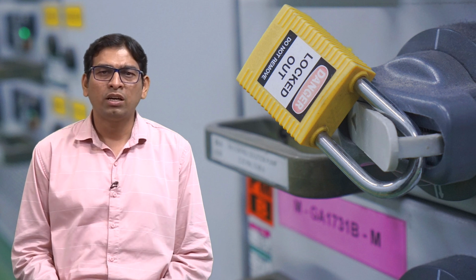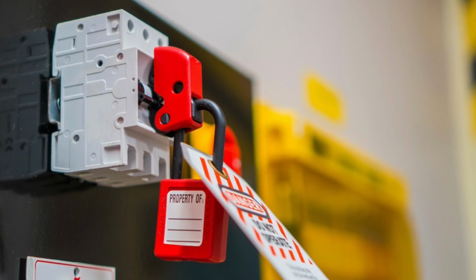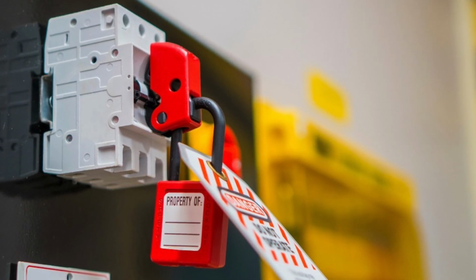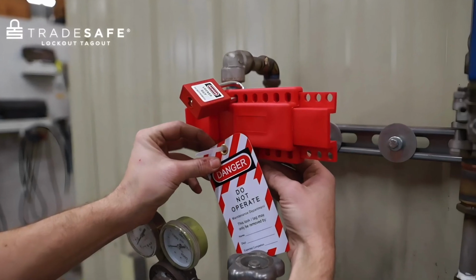Once the work on the locked out machine is completed, proper lockout tagout release procedures must be followed to return it to service. First, you need to remove all the non-essential tools and other materials from around the machine. Next, clear any affected employees from the immediate area. Then you should check to make sure that the machine is ready to operate. This includes verifying there is no load on any electrical circuits.